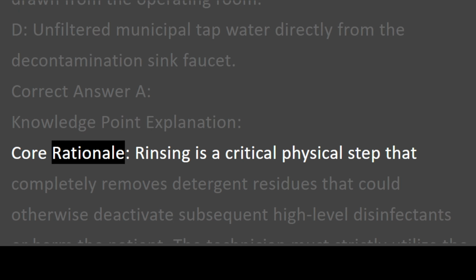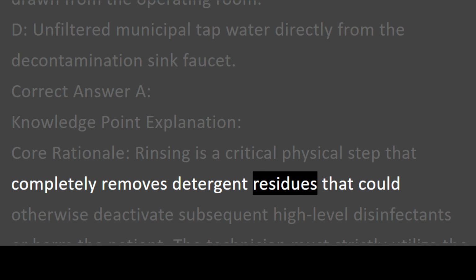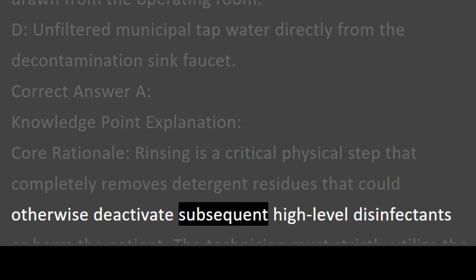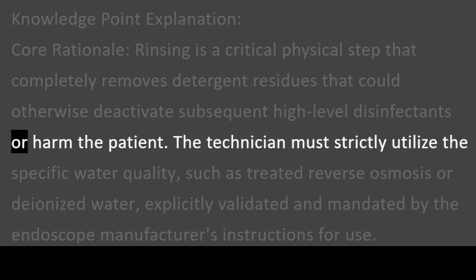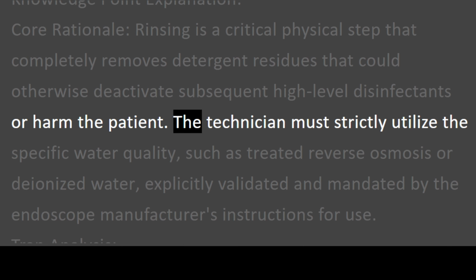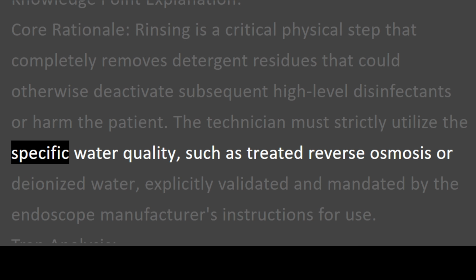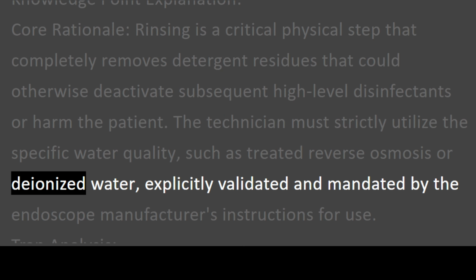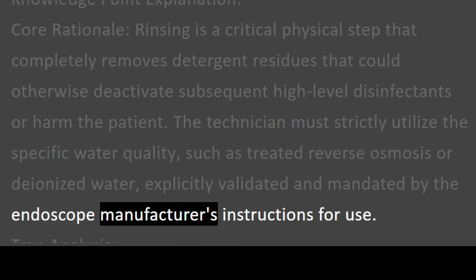Core rationale. Rinsing is a critical physical step that completely removes detergent residues that could otherwise deactivate subsequent high-level disinfectants or harm the patient. The technician must strictly utilize the specific water quality, such as treated reverse osmosis or deionized water, explicitly validated and mandated by the endoscope manufacturer's instructions for use.